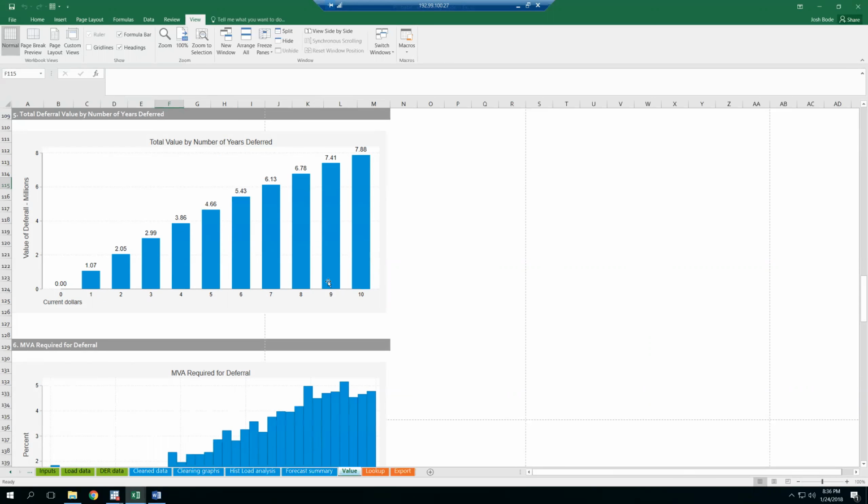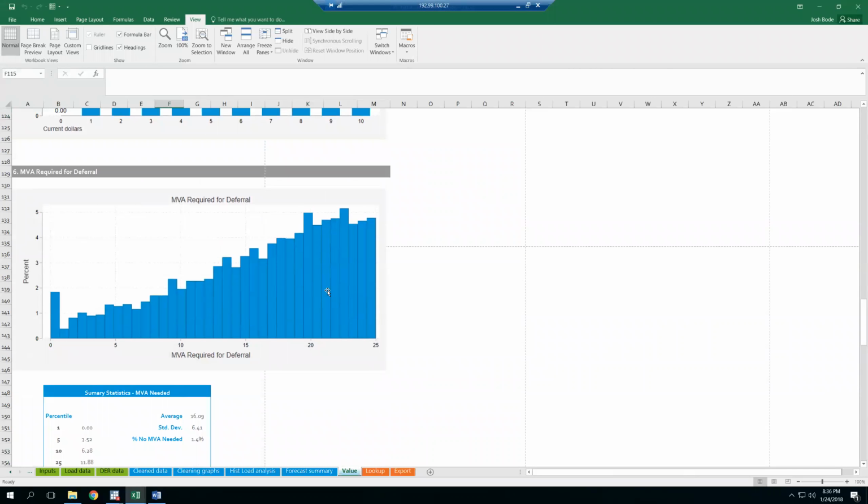Chart number 6 is kind of saying here's the megawatts required for each of the deferrals. And it's capped, based on our inputs, at 20% of the load, and it's capped at being at most 10 years. So one of those came out to say, here's what the number looks like. And the reason it varies is that this one really assumes that you can ramp up the resources in tandem with the need. So it assumes relatively great foresight.